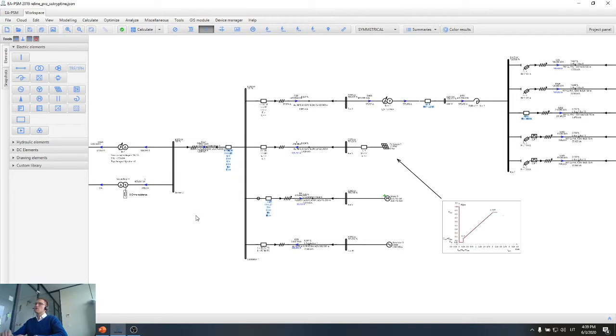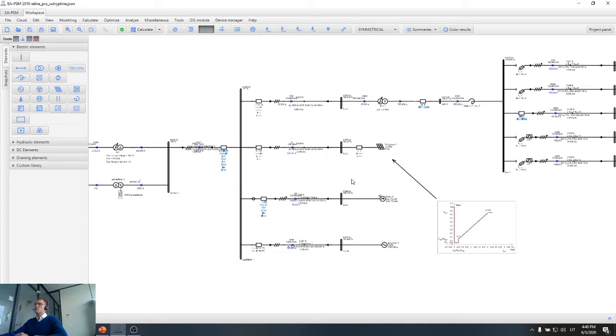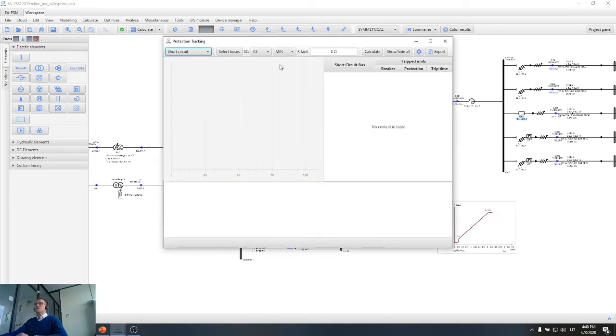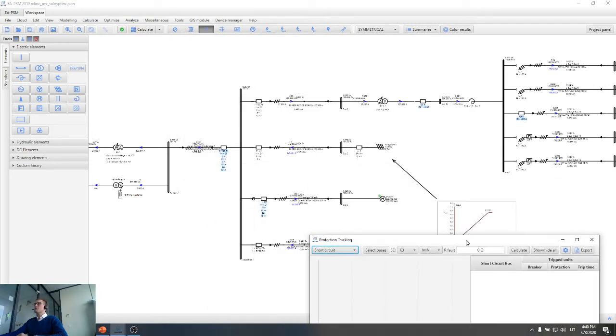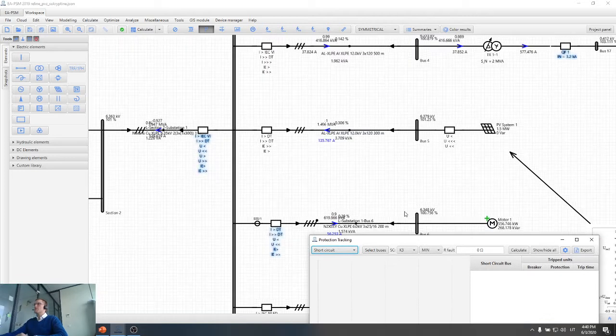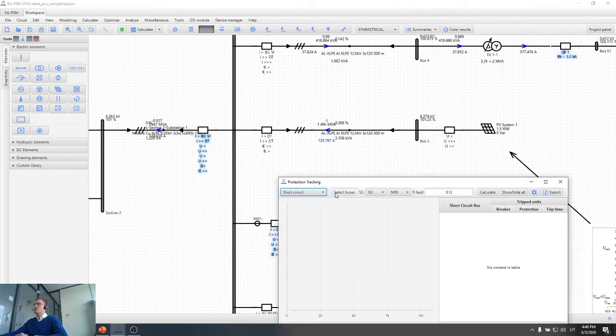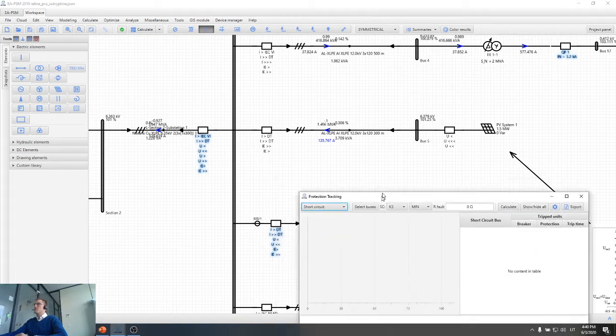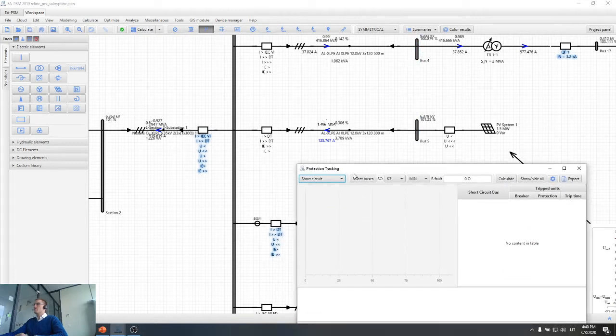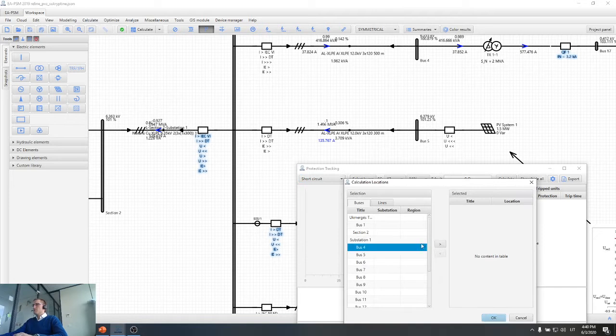However, when we do the protection coordination, we also need to check how our protection coordination will work in case of different scenarios. So for that reason we have a protection tracking feature. This is a feature which allows to simulate different scenarios in the network and to see operation of the protection devices. So let's try to simulate bus 4 and bus 5 short circuits. Bus 4 and bus 5.